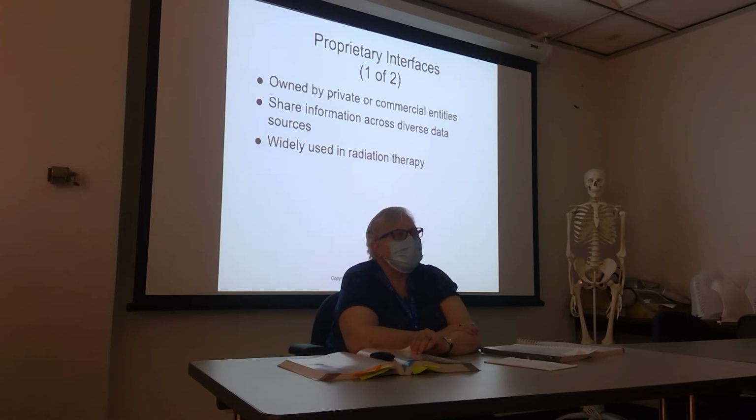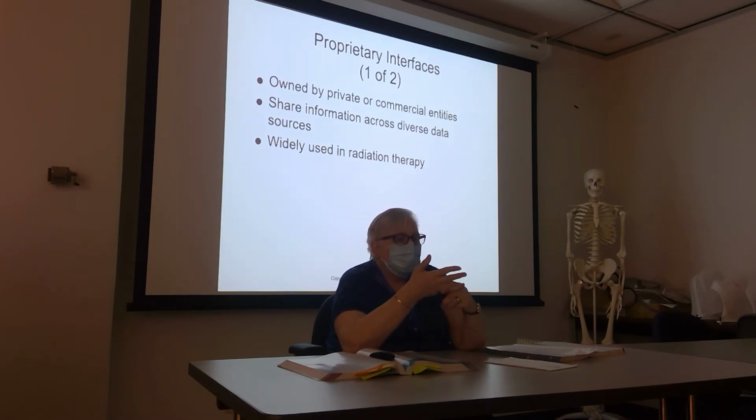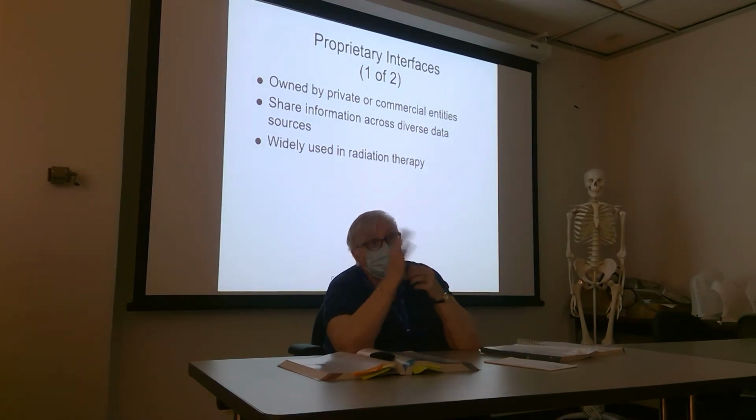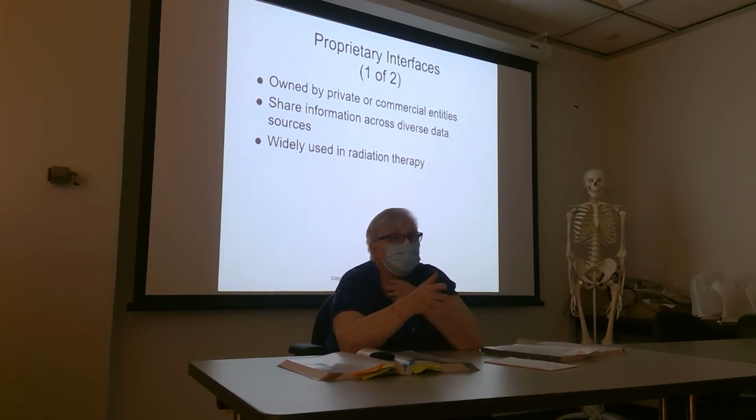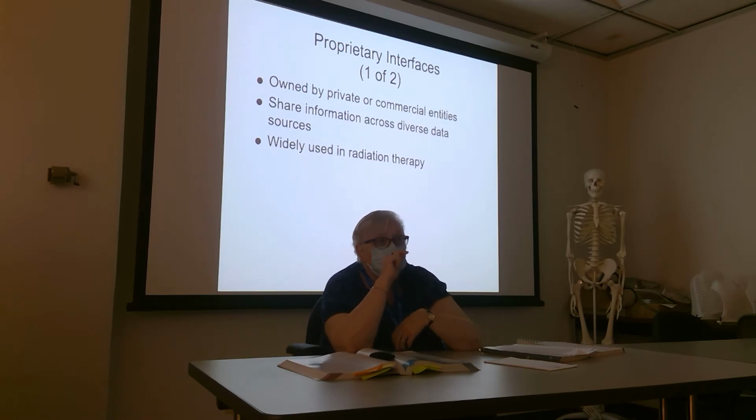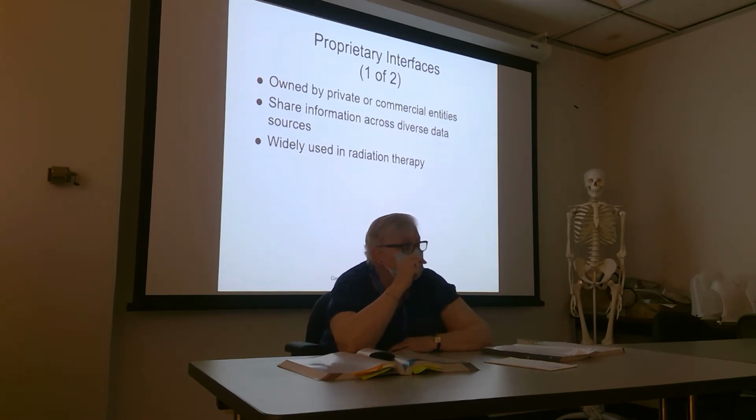It is theoretically possible to treat. However, you have no idea what the dose is. You have no idea what the field size is because it's all on the computer system. You can actually treat on override, but that's dangerous because you have no fail-safes, you have no backups. So it is theoretically possible, but it is not done because you have no safeguards.